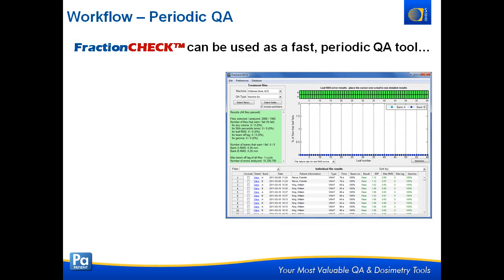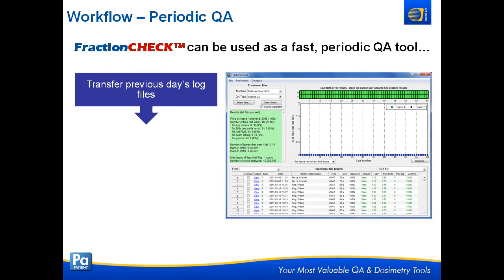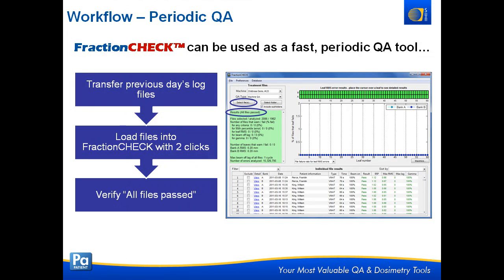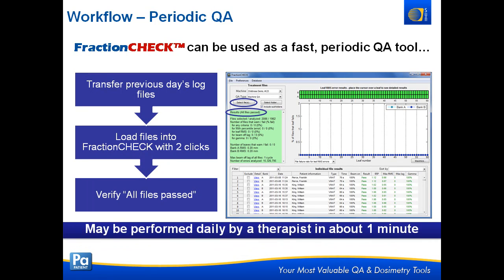So, how does this work in the clinic? It can be used for periodic QA — you take your previous day's log files, load them into FractionCheck with two clicks, and it processes about 250 fields a minute, which is typically about the number of fields you'll deliver in one day. In about one minute, it should pop up and say all files passed. This is very simple — you can even have your therapist do that in about one minute a day.